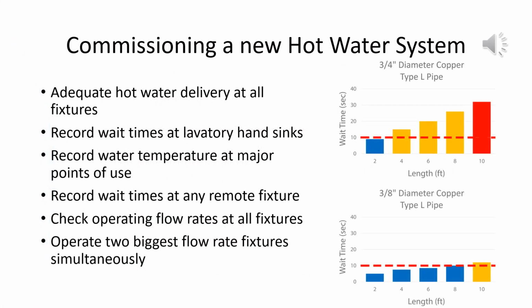Here are some best practices for commissioning a new hot water system. The operator should measure the delivery temperature at all fixtures with a handheld temperature sensor. The wait time for hot water delivery should be measured at lavatory hand sinks. Health department officials will sometimes perform this test during a sanitation inspection, so it is a best practice here. Determining the wait times at any remote fixture is especially important because they tend to have the biggest hot water delivery failures. Operators should use the catch and weigh test to check the operating flow rates at all fixtures. The flow rate should match the manufacturer's specifications.